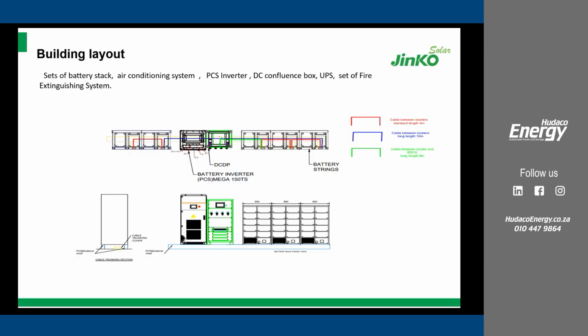Then for the equipment, look at this building layout. This is where we have the batteries, and we also need to have the PCS as well. We also need to have the DC cabinet. The DC cabinet is basically where we have the DC breakers. These are the DC breakers where we're running the cables from each of the battery racks to the DC switch, and of course from the DC switch to the PCS as well. So we need to basically plan for that as well.